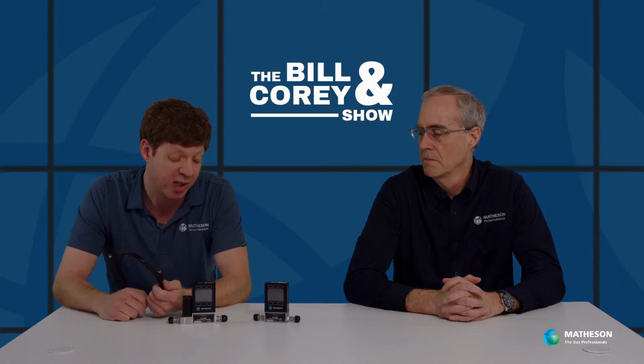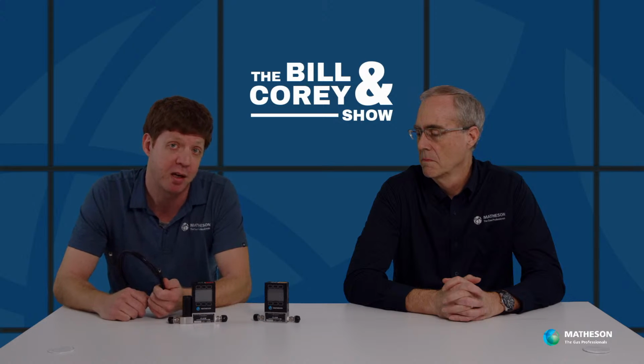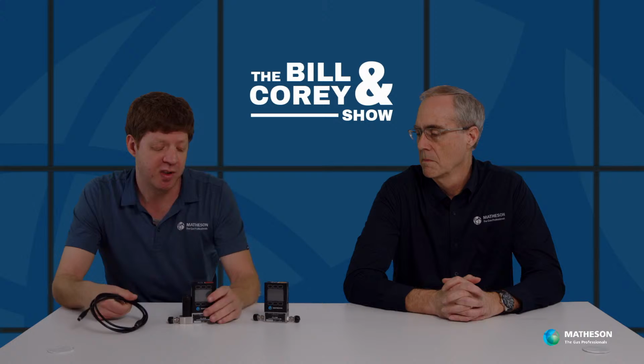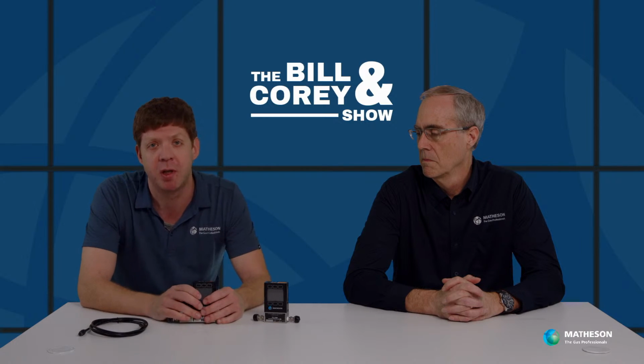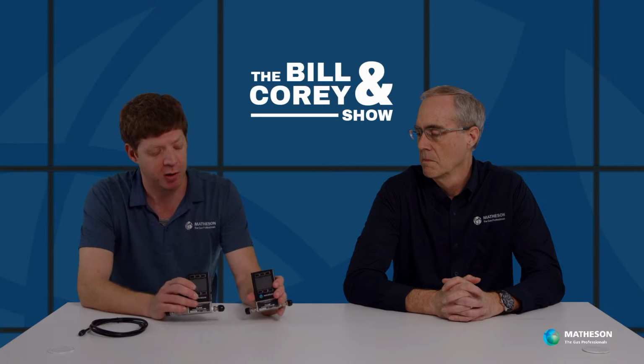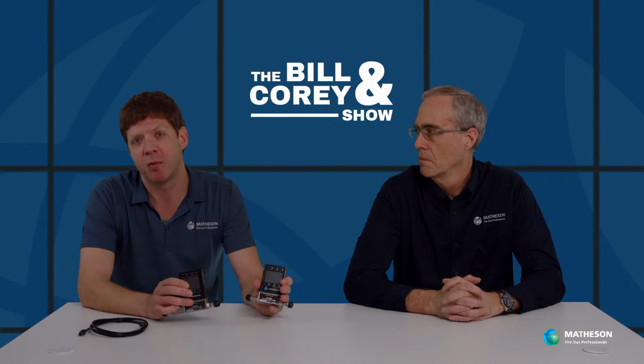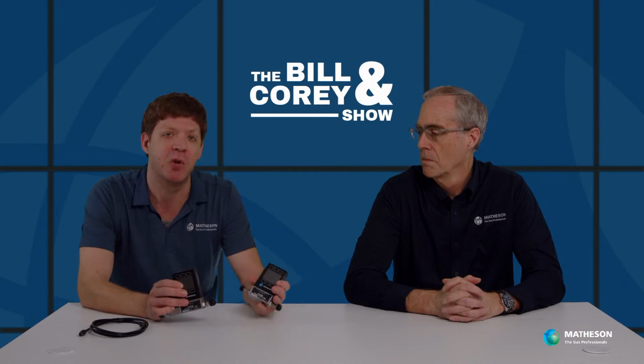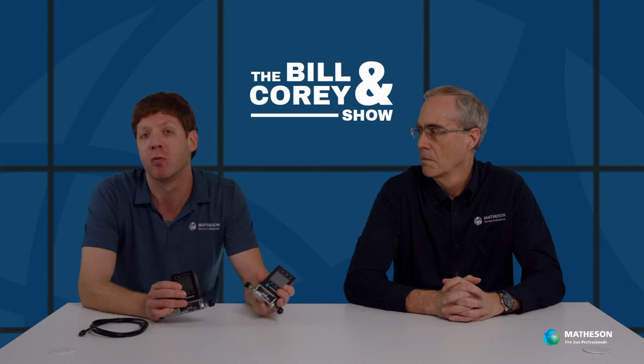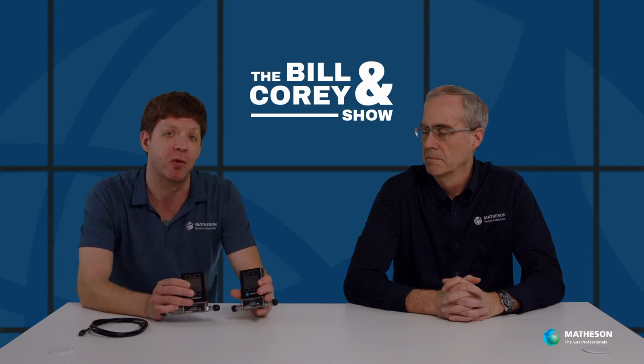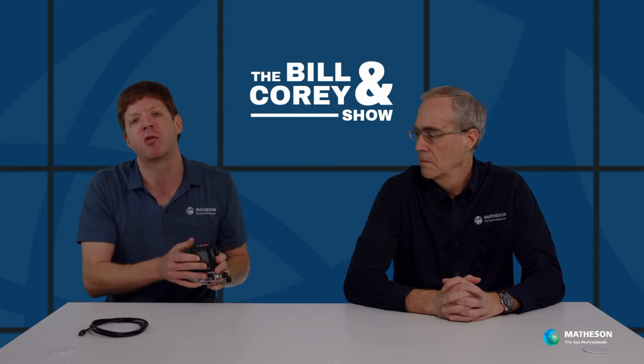And these are also intrinsically safe. So the person wanted methane, and they are intrinsically safe. If you want a corrosive material, though, you'll have to special order. They go up to about 20 SLPM on our online store, but if you need a higher flow rate, within reason, obviously we can go higher than 20 SLPM. And that's measured in air. That's 20 SLPM air.